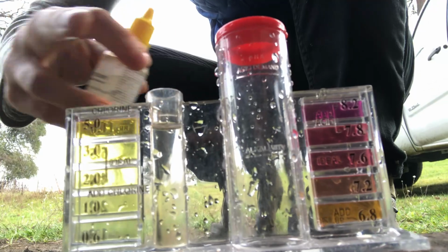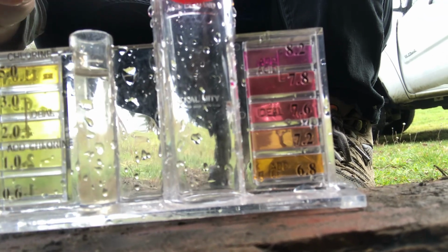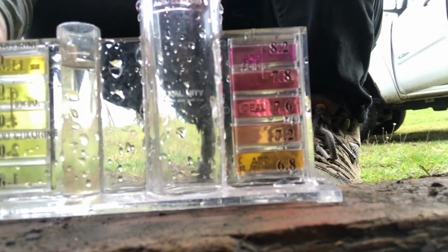Rain has stopped, and it's been an hour and 10 minutes of draining the well, and we finally have no chlorine detection. So I have some well water in here. Yay! Okay, time to drain the tank again and get fresh water from this well into our hose bibs and fire hydrants.